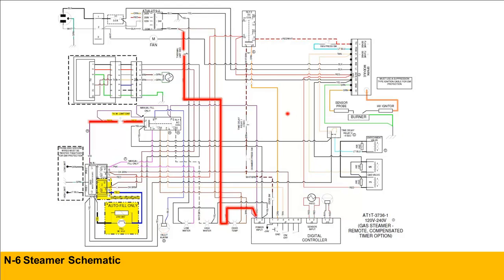So the diagnostic side of it is, if the high water switch is open, once again, we'll have to figure out if it's the float ball, the switch, or possibly the AC relay. Now, as Dan stated, as soon as you plug the unit in, this AC relay will energize. So troubleshooting-wise, the first thing we'll check, if the relay is not energizing, is whether we actually have 24 volts AC going to the relay. If we have 24 volts going to the AC relay, that tells me my switch is good and also my float. So at that point, if there's voltage going to the part, it appears we have a defective relay.